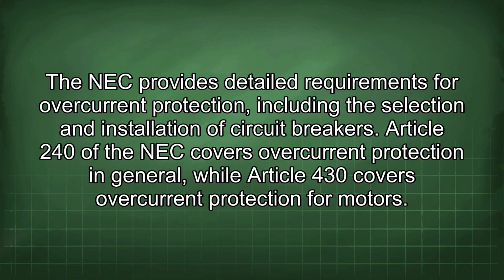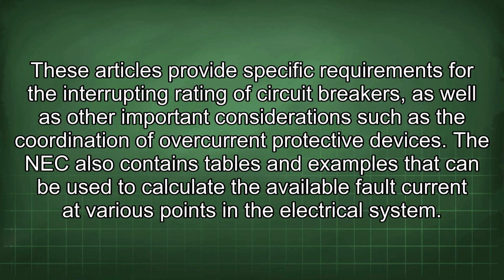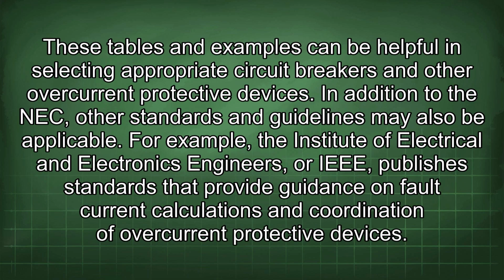The NEC provides detailed requirements for overcurrent protection, including the selection and installation of circuit breakers. Article 240 of the NEC covers overcurrent protection in general, while Article 430 covers overcurrent protection for motors. These articles provide specific requirements for the interrupting rating of circuit breakers, as well as other important considerations such as the coordination of overcurrent protective devices. The NEC also contains tables and examples that can be used to calculate the available fault current at various points in the electrical system. These tables and examples can be helpful in selecting appropriate circuit breakers and other overcurrent protective devices. In addition to the NEC, other standards and guidelines may also be applicable.